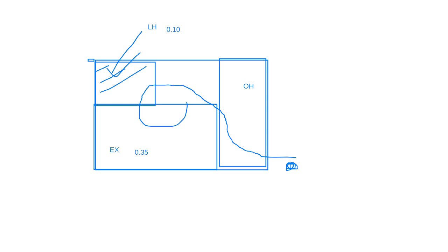We have to perform different calculations. One for the light hazard areas, because it is the most remote, to support the pressure requirement there, and we have to do the hydraulic calculation for the extra hazard areas, and for the ordinary hazard area. Then we have to submit the plan to the consultant so that he will see how we are getting the pressure and flow in all the buildings.